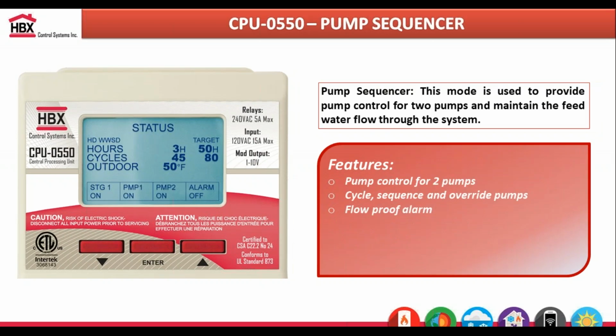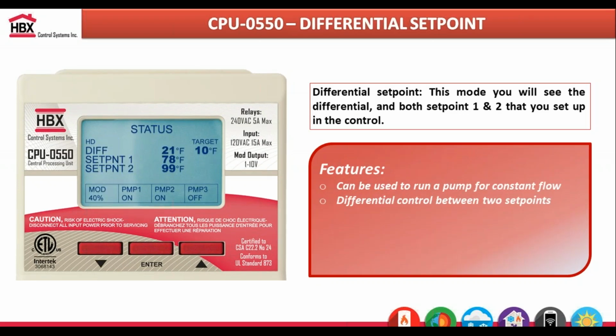If you want to use this as a pump sequencer, we can do two pumps, and you can control them manually or based off outdoor reset, and they'll sequence based off time or based off runtime cycles. You also get a flow proof alarm as well. So if your pumps are running dry, they'll automatically shut off to prevent any damage to your pumps.